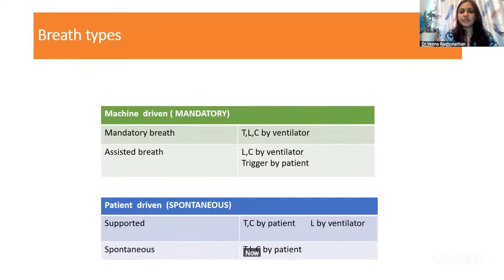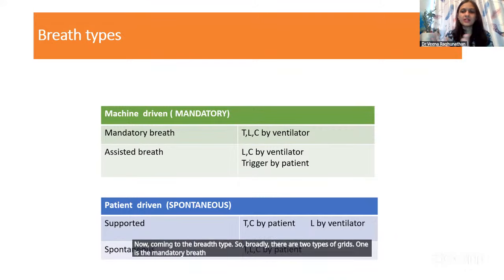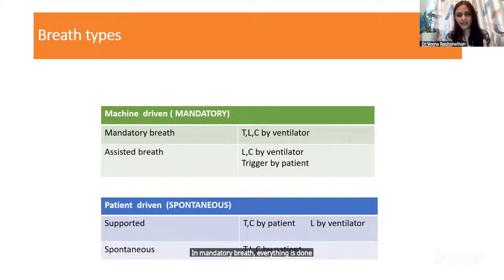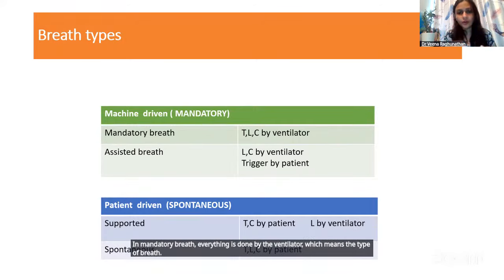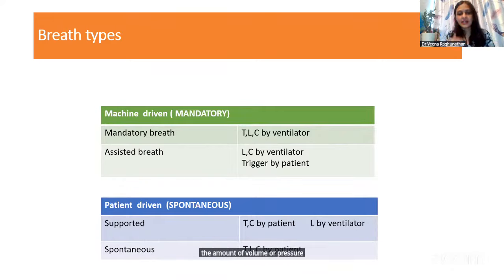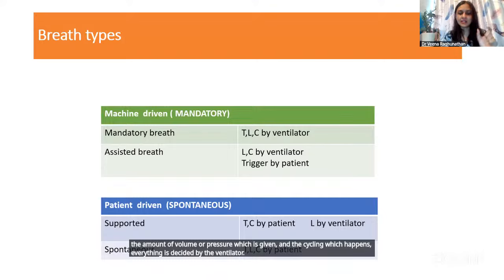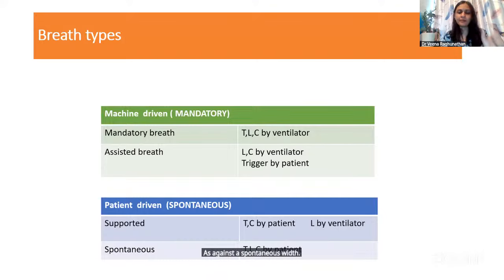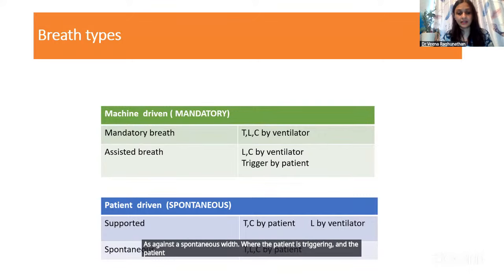Now coming to the breath type. Broadly, there are two types of breaths: one is the mandatory breath and one is the spontaneous breath. What do we mean by mandatory breath? In a mandatory breath, everything is done by the ventilator, which means the type of breath, the amount of volume or pressure which is given, and the cycling which happens, everything is decided by the ventilator. As against a spontaneous breath, where the patient is triggering and the patient is cycling the breath.